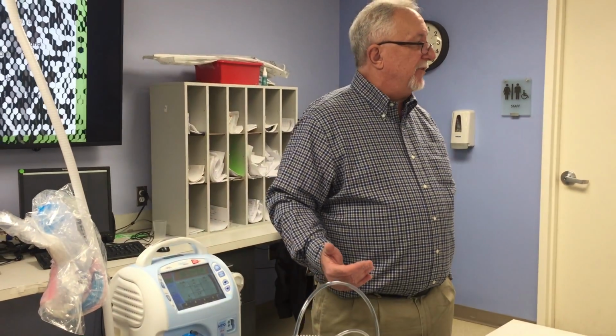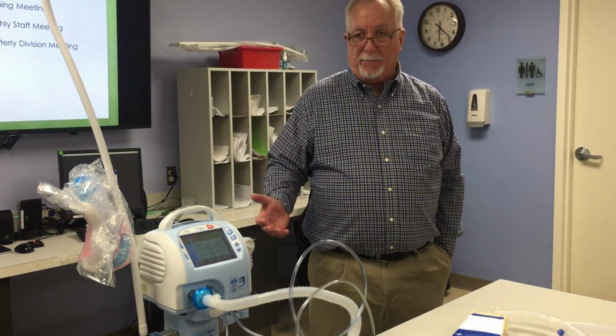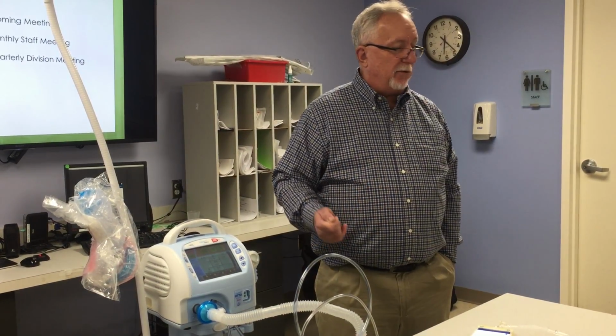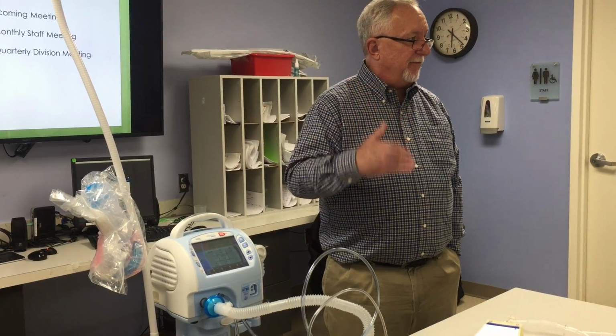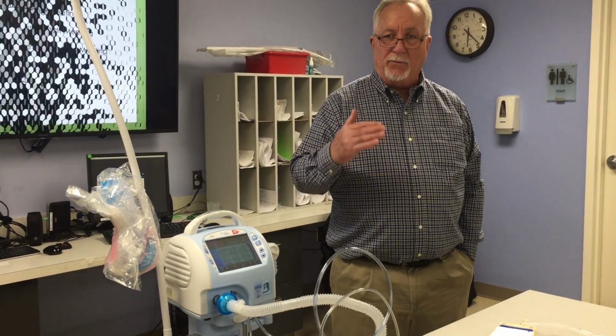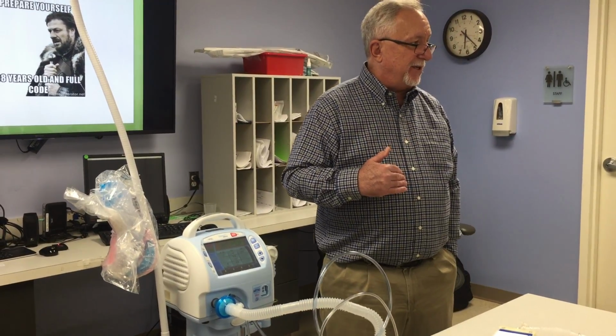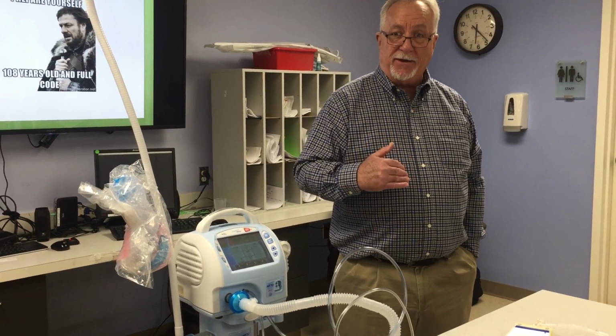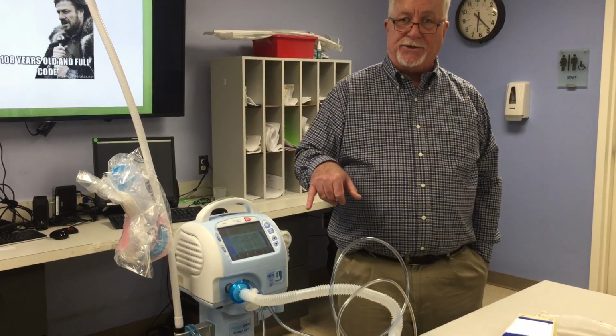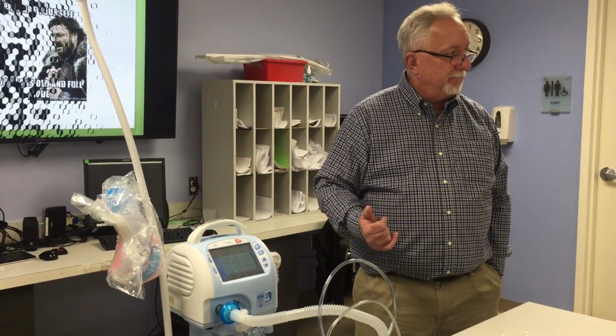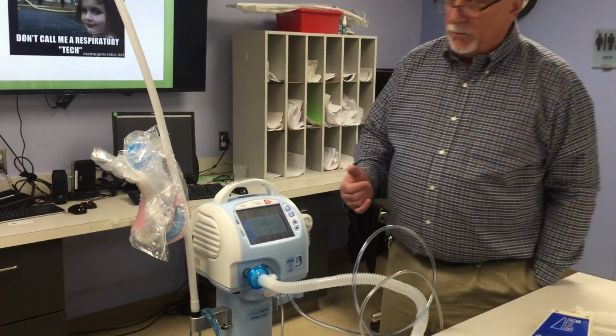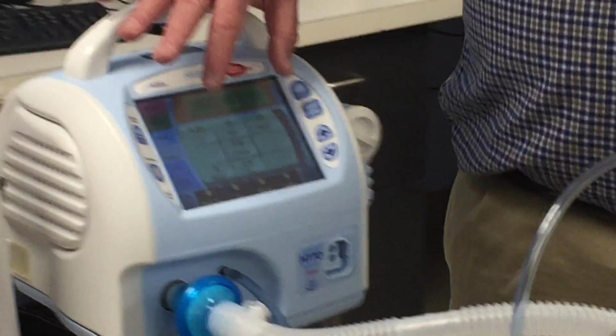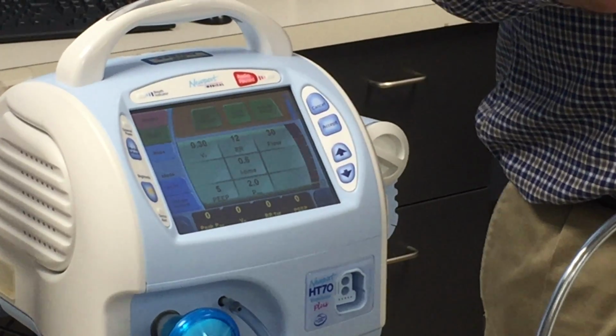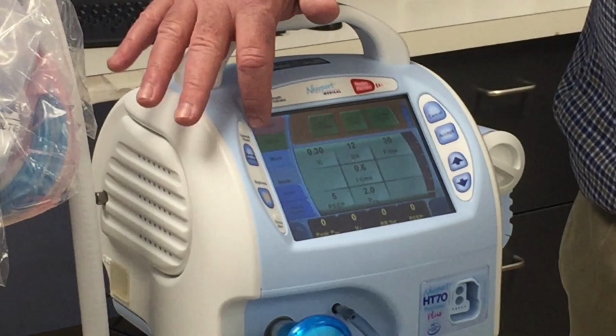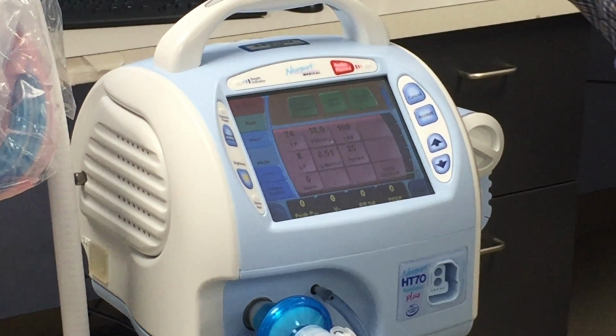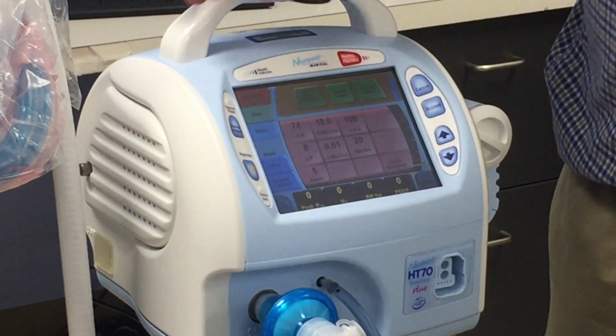There is an event log inside there, and it'll hold 1,000 events. So if you ever had a problem with the ventilator and you want to go back, you can download that with a thumb drive and look at the events and see what changes were made, with date and time stamps on each one. Every time you press the screen or press a reset button, it records that. You can see it's color coded. Green is our settings, and if I hit alarms, you can see that's pink or red. So green is our settings, red are alarms.